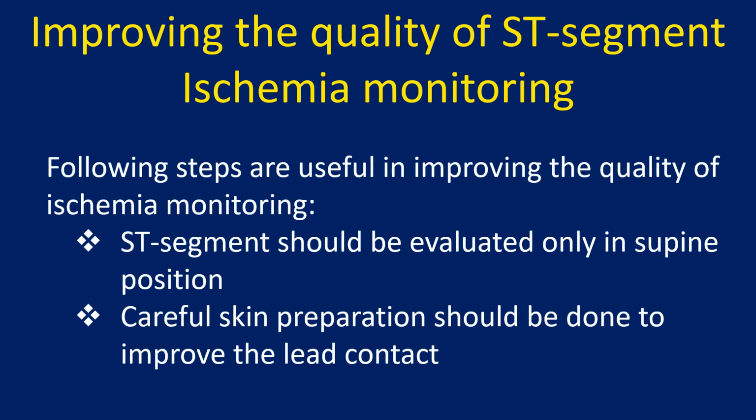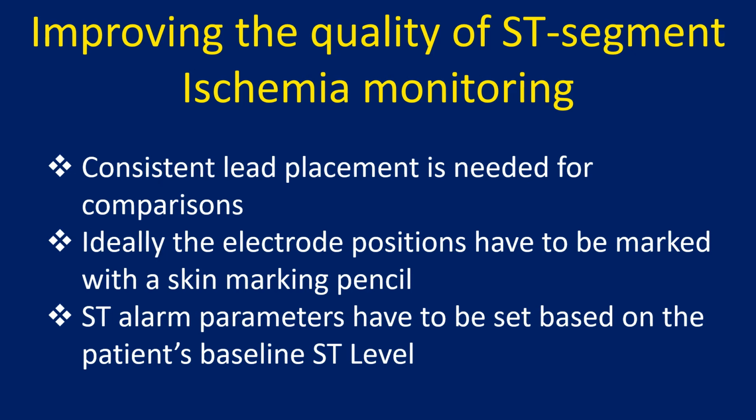Careful skin preparation should be done to improve the lead contact. Consistent lead placement is needed for comparisons. Ideally, the electrode positions have to be marked with a skin marking pencil. ST alarm parameters have to be set based on the patient's baseline ST level.